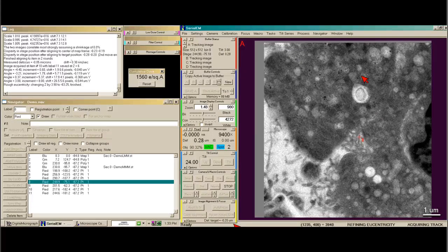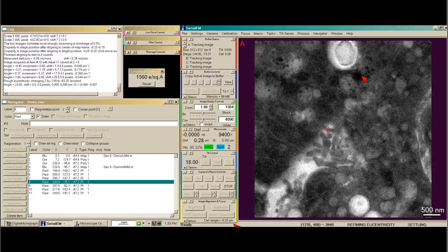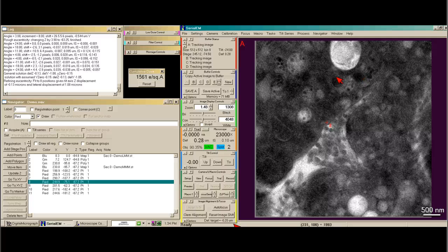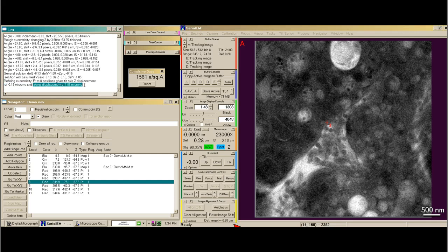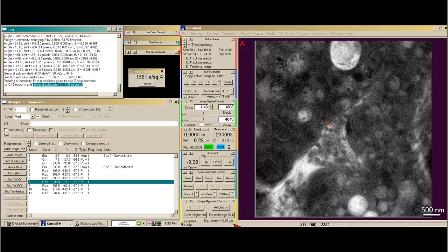For fine eucentricity, we go up in mag to around 10,000X, and we tilt from plus 24 to minus 24. Fine eucentricity has finished, and if we look at the log file, we have this line called lateral displacement of 1.08 microns. This is a measurement of the distance between the optical axis and the tilt axis, and the closer to zero this is, the better, in the sense that you don't have to track as often or do image shift resets during tilt series acquisition. I like mine to be around plus or minus 1 micron away from zero.